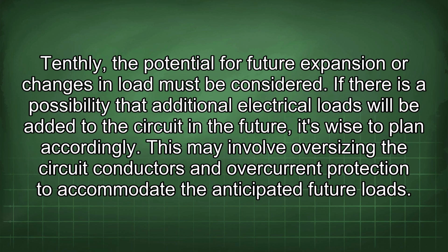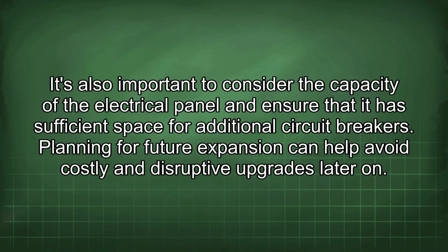Tenthly, the potential for future expansion or changes in load must be considered. If there is a possibility that additional electrical loads will be added to the circuit in the future, it's wise to plan accordingly. This may involve oversizing the circuit conductors and overcurrent protection to accommodate the anticipated future loads. It's also important to consider the capacity of the electrical panel and ensure that it has sufficient space for additional circuit breakers. Planning for future expansion can help avoid costly and disruptive upgrades later on.